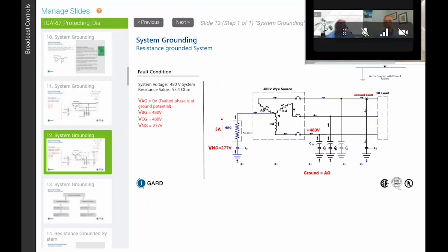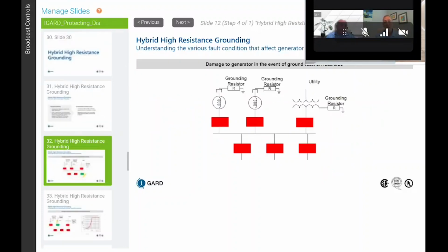All right, Sergio, Scott submitted this question: for parallel generators with neutral resistors grounded individually at the generator, harmonics can still be an issue. Can the addition of a grounded zigzag transformer help with this?